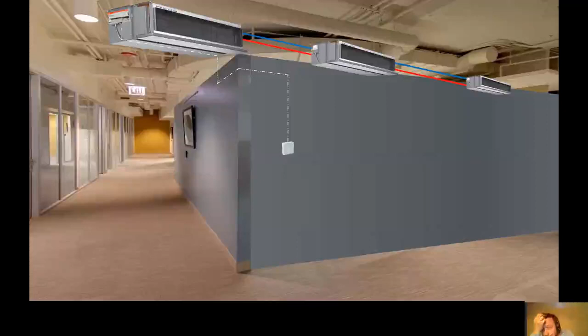What we've got here is an open plan office, and we've got 3 fan coil units in what's called a master slave configuration. So we have the master controller on the side there with the main unit with the sensor on the wall. The subsequent units are slaves, which effectively means they follow the same command as the primary or the master unit. So in this consideration, we are cooling based on a set point requirement. That's absolutely fine. There's no problem with that at all. All units are doing the same thing.